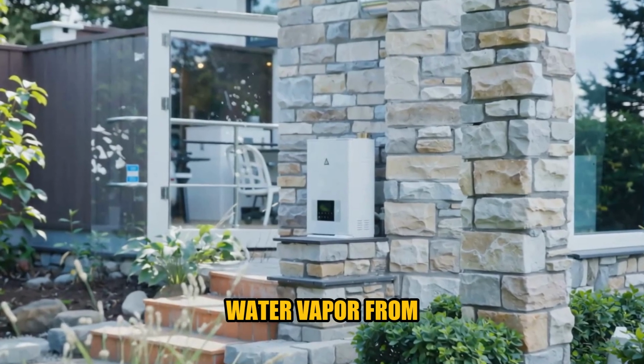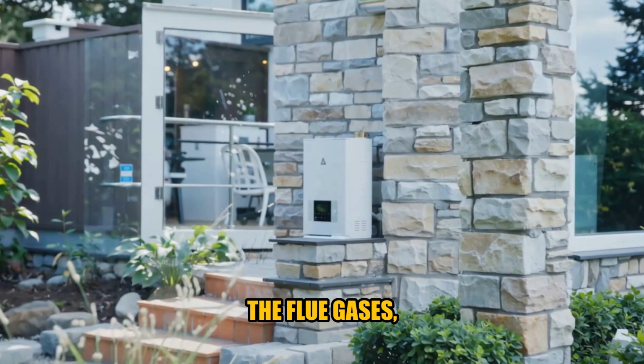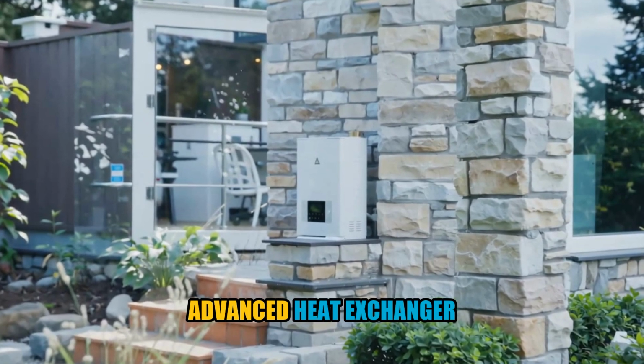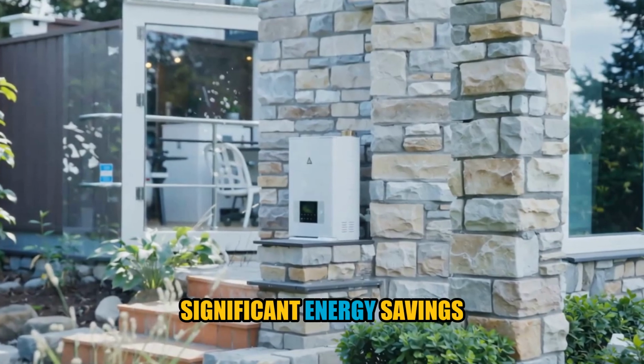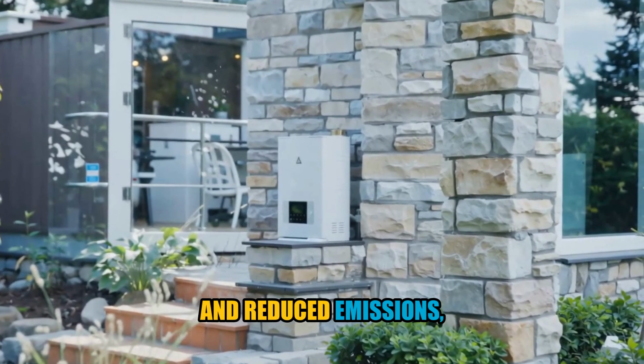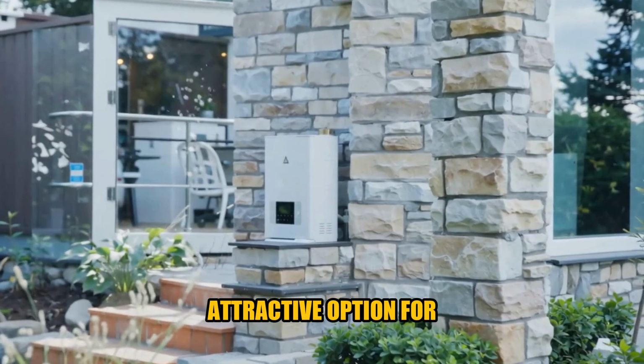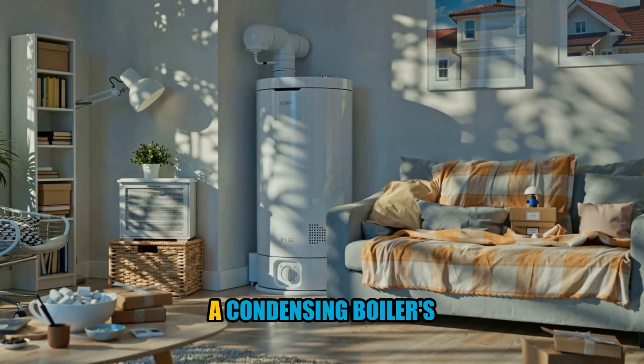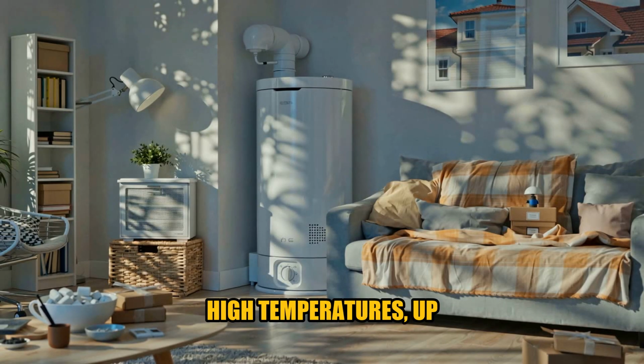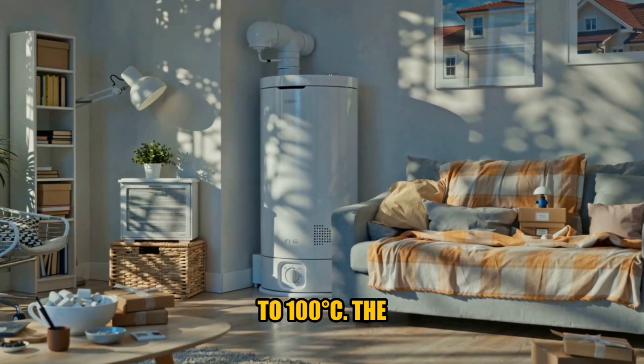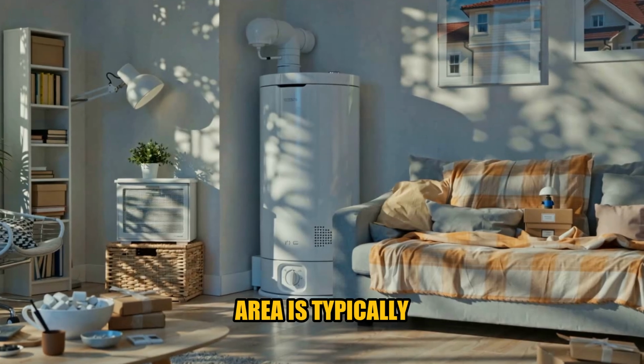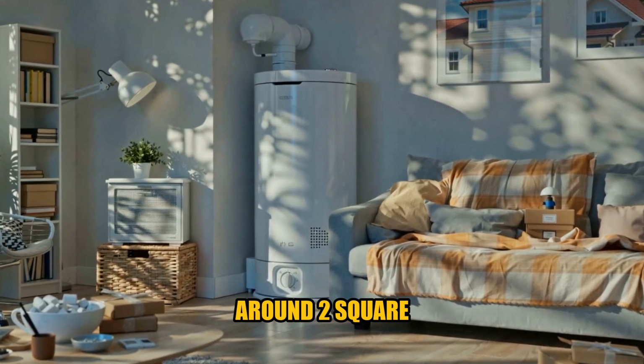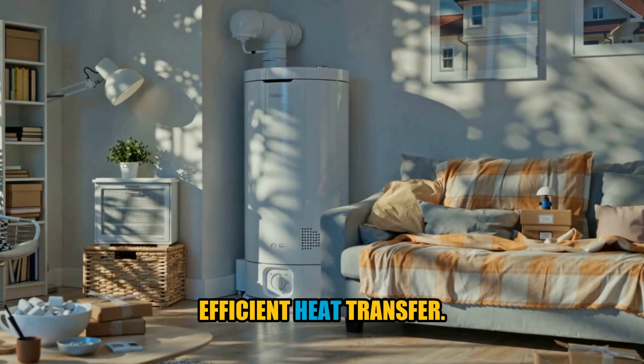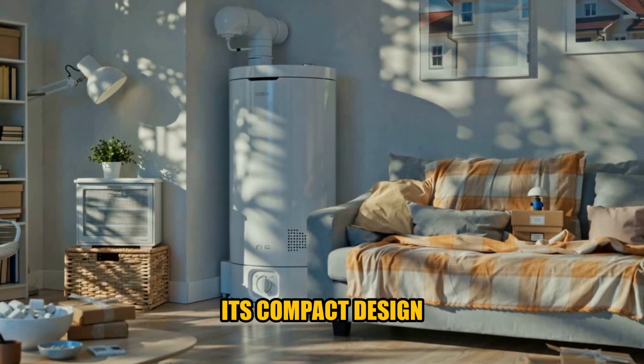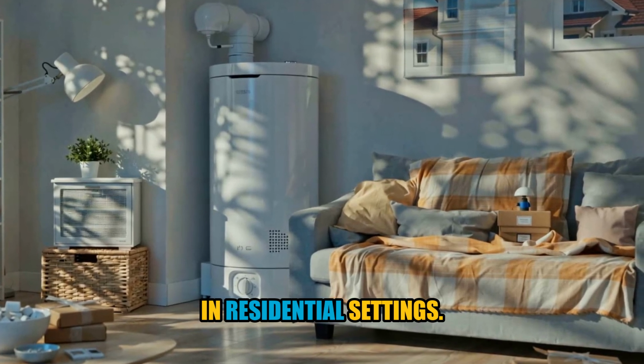The boiler's ability to condense water vapor from the flue gases, combined with its advanced heat exchanger design, results in significant energy savings and reduced emissions, making it an attractive option for residential heating systems. The condensing boiler's heat exchanger is designed to withstand high temperatures, up to 100 °C. The heat exchanger's surface area is typically around 2 square meters, allowing for efficient heat transfer. Its compact design enables easy installation in residential settings.